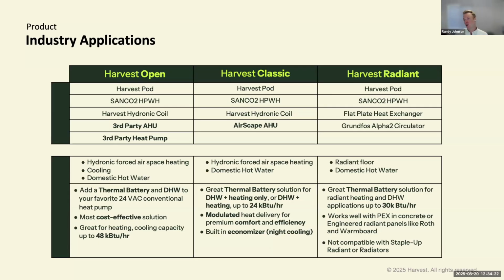From a design perspective, if we were looking at a radiant application, let's say in Colorado as an example, we would size this for 30 kBtu an hour. We would do two standing outdoor units plumbed in parallel to provide the output of about 30 kBtu an hour. And then depending on the overall heating load, if you're right near the edge, or for resiliency, we typically recommend an inline electric booster. That would run on a sensor and come off of the hot line coming out of the top of the tank. We just spec a Rheem 7.6 kW, and that's ultimately a 30 amp double pole breaker. The water is only 110 degrees coming out of the tank. That's not enough for our heating application. We're going to boost that up to 150 before it hits the heat plate exchanger.